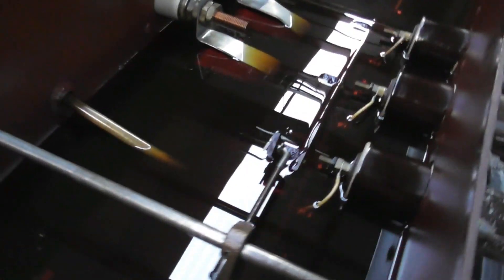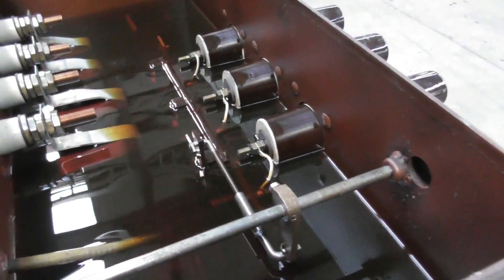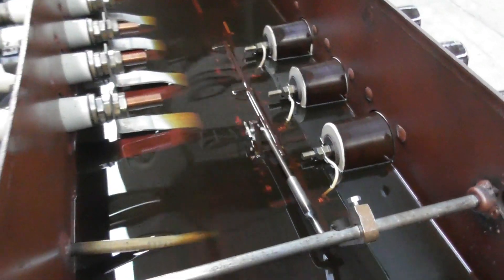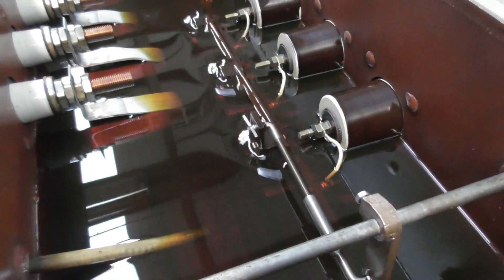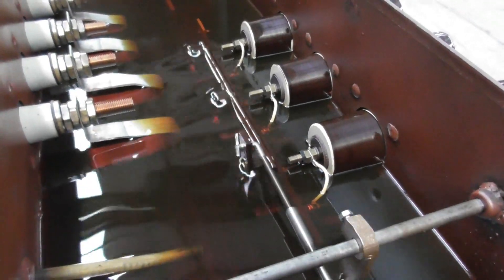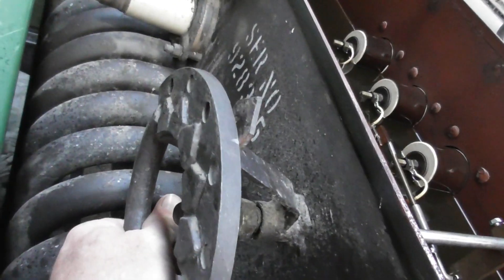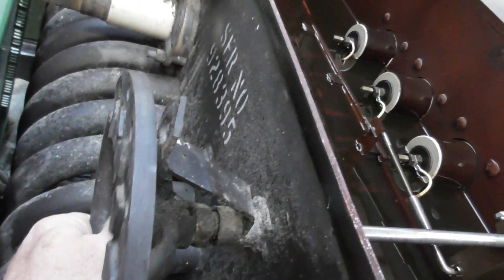As I said, it's for voltage control. Click. I've got the rollers on the tap changer, and I have one of those in my archives at home so I can give a bit more detail. It's sitting on tap 2, which is the 11 kV tap. Taking the securing bolt out — there you go. I'll add this onto a card on the video — it's just beautiful.